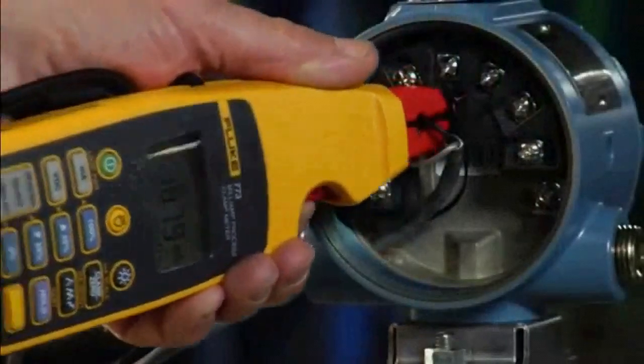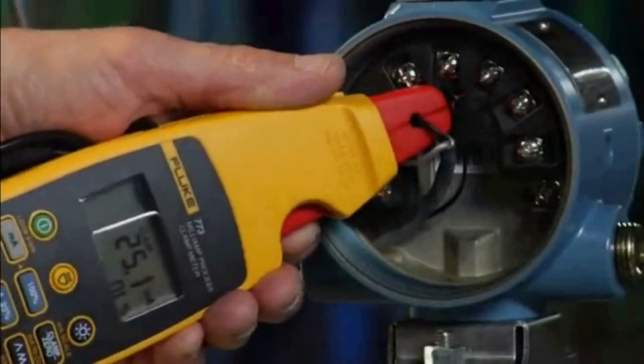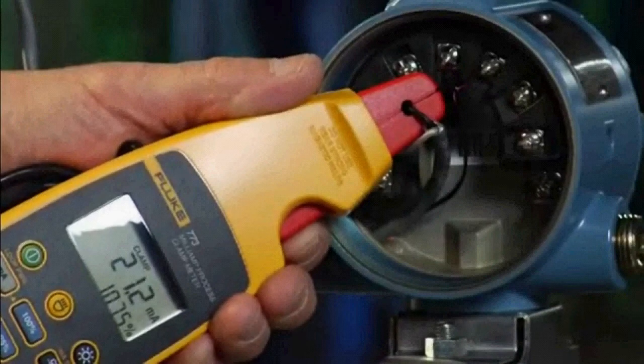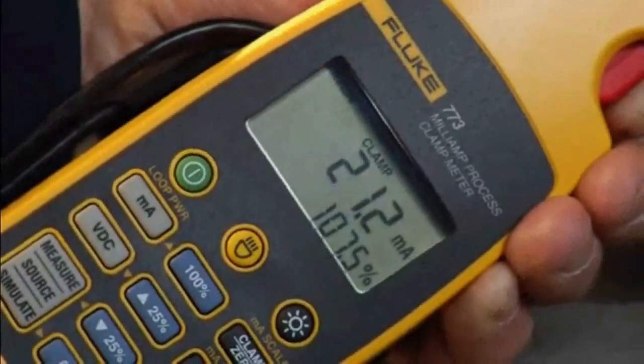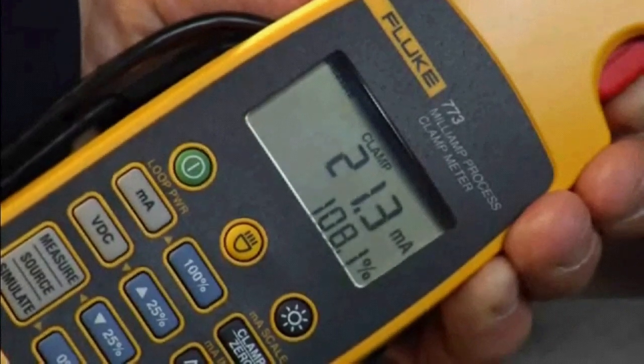First, clip the Fluke 773 onto one of the milliamp signal wires to make the measurement. An indication of 21 milliamp shows that, indeed, the loop is in alarm and that further troubleshooting is required.